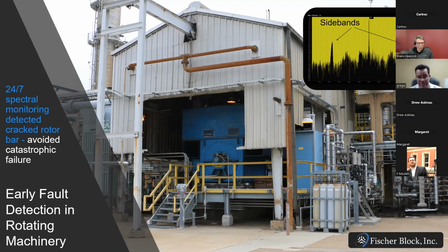Oh yeah. And this is an example here of a large motor. We're monitoring 24/7 current consumption as well as the voltages, and that top right frequency spectrum there, you can see those side bands. The fundamental there is in the center at 60 hertz, and as rotor joints degrade and become hot spots before they begin to even crack or have any type of vibration associated, we will see the distortion in the 60 hertz signal, and it actually manifests as side bands. The distance from 60 is a function of the slip frequency, so the rotational speed of the motor versus the grid's running at 3,600 RPMs, which is 60 hertz. The motor will be a little bit slower than that, and that difference is the slip. So we know where to look on the frequency spectrum, but in that case there, it's quite obvious that those sidebands are due to some type of distortion.